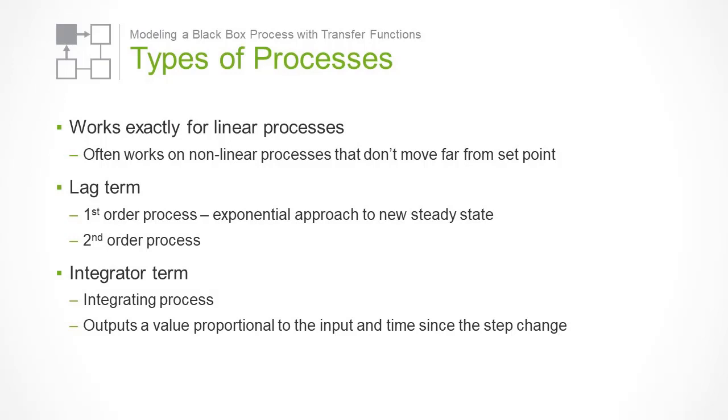Another commonly encountered term is the integrator term. A process that can be described by the integrator term is often called an integrating process. The response of a first-order process that's at steady state to a step or instantaneous change in the input is an exponential approach to its new steady state value. An integrating process responds to a step change by outputting a value proportional to the input and the time since the change.